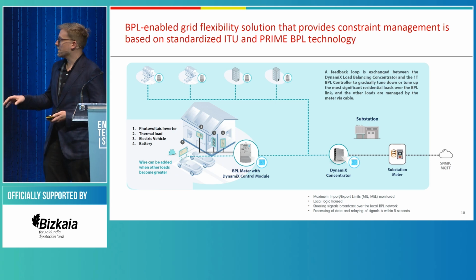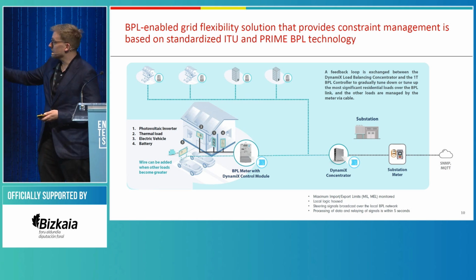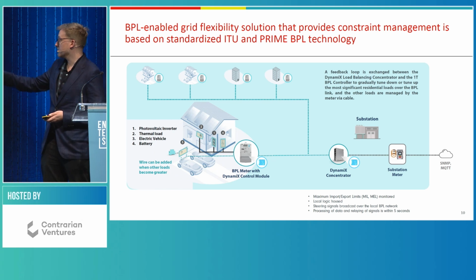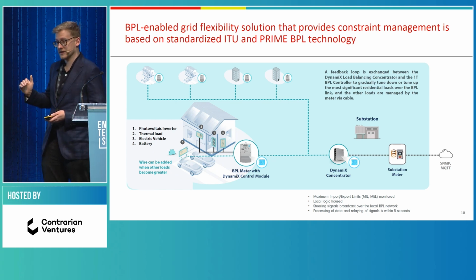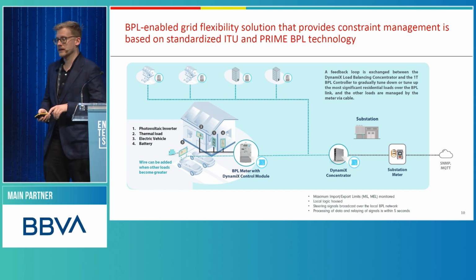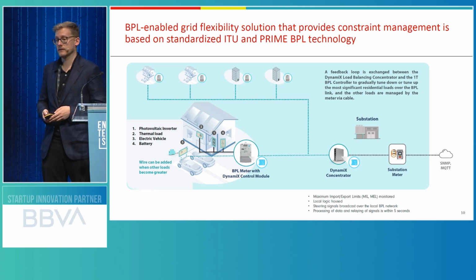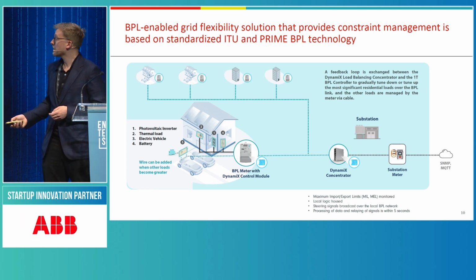In practice, the secondary substation, where you see the DynamiX Concentrator, is connected to a substation meter, allowing us to control the import-export limitations of that transformer nearly in real time. Our ability to run these algorithms locally inside the grid, rather than in the cloud, allows us to respond far quicker than a cloud-based solution could.